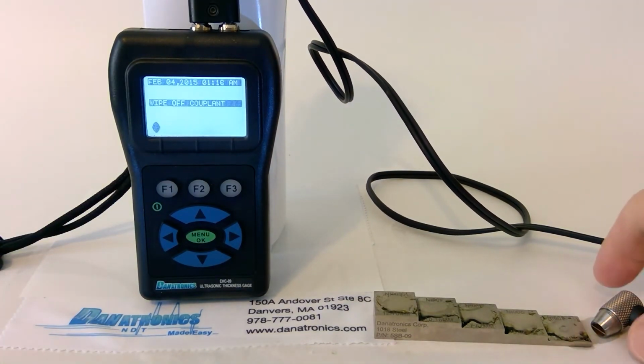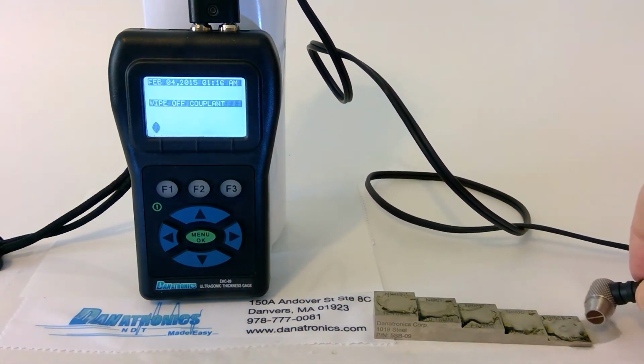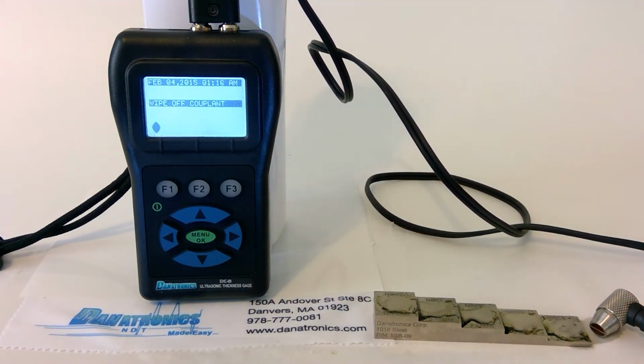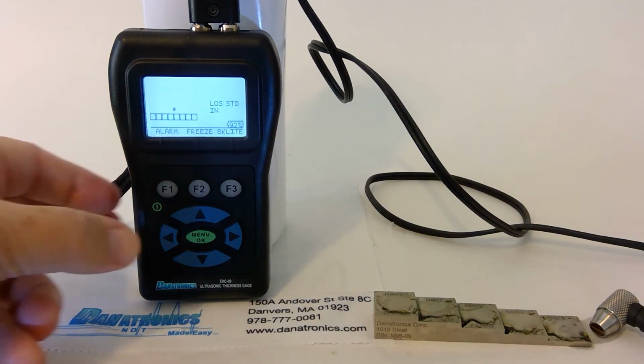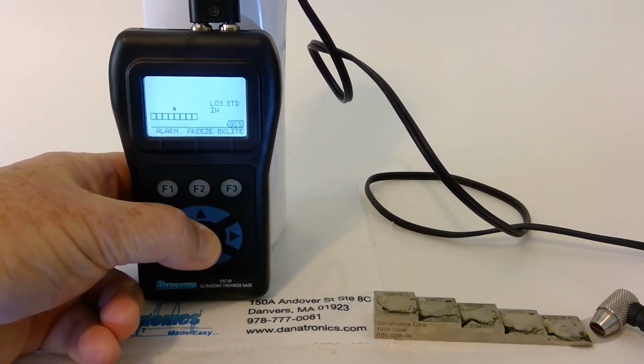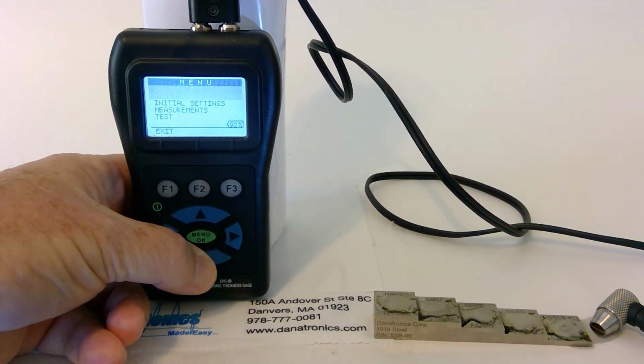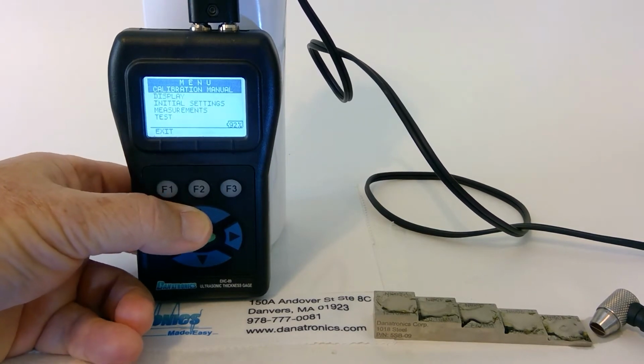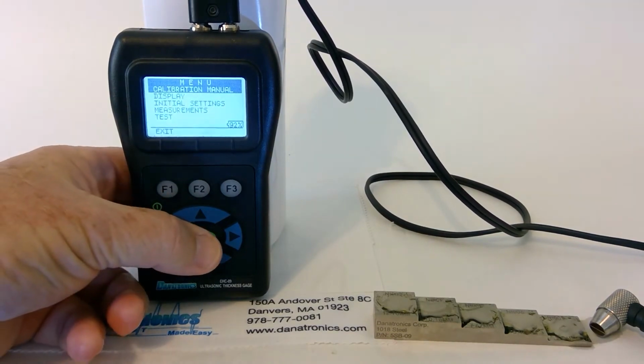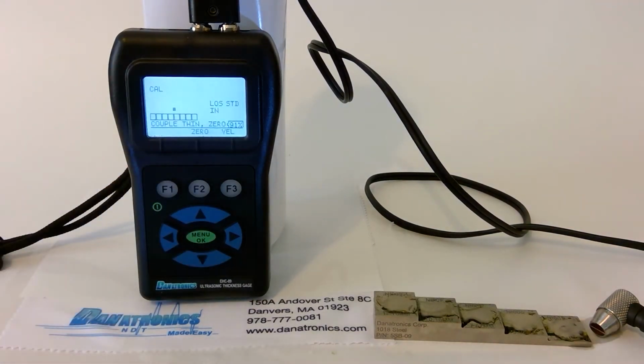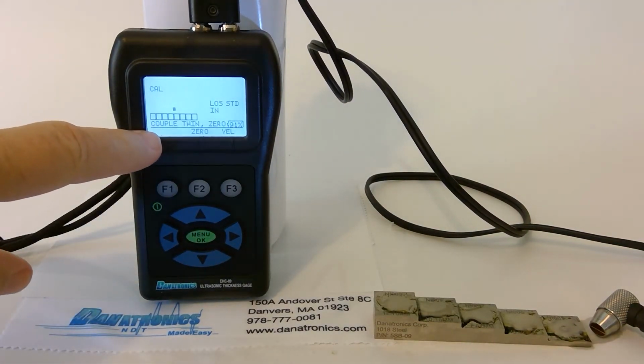It's asking us to wipe off the couplant. Then it will perform the auto zero calculation. Now that that's complete, we will do our calibration. We press the menu button. With the up or down arrow key, we highlight calibration and we hit OK. Now we follow the directions on the bottom of the screen located here.